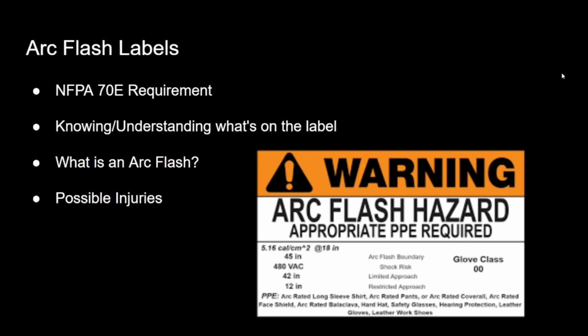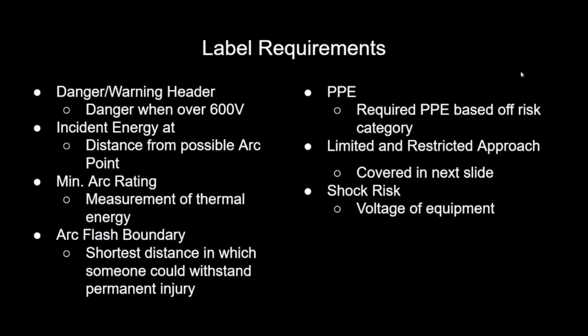Arc flash labels fall into the labeling category of the NFPA 70E. We're going to cover knowing and understanding what's on these labels, what an arc flash is, and possible injuries from an arc flash. Required on the label is the danger or warning header. Normally you'll see warning. If it's anything over 600 volts, it'll say danger. The incident energy at is the distance from a possible arc point to the head or body of the person performing the work. The minimum arc rating is a measurement of thermal energy, how big that blast is going to be if there is an arc, or how small that blast can be.